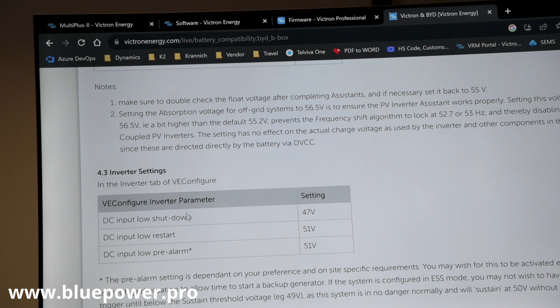Here's one inverter setting. That's where we are currently. If I move this to the side, I can see our DC input low shutdown. That's the value at which the inverter is going to disconnect from the battery to save the battery or no longer discharge the battery. It's a must-have, or must be configured correctly, for lithium batteries. Otherwise, your BMS trips before your inverter disconnects, and then you're going to struggle to recover that BMS. Some BMSs are more forgiving, but most of them you're going to have to get a battery out on site or a charger or some other source to recover the battery. So make sure that's set according to what the manufacturer recommends, maybe even slightly higher.